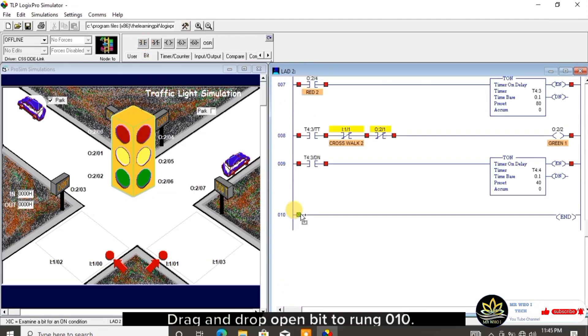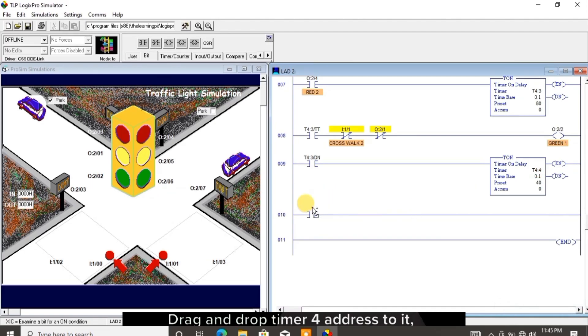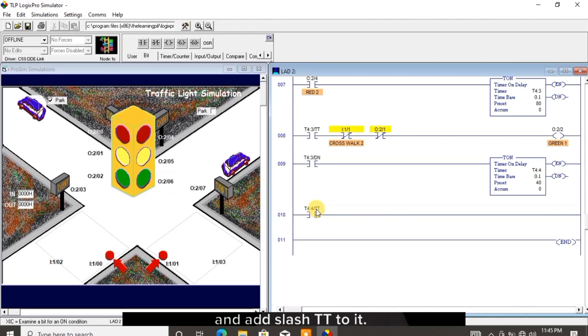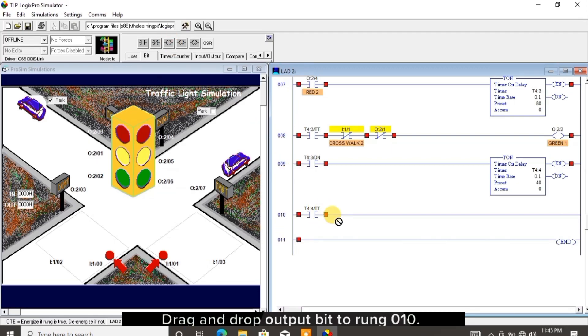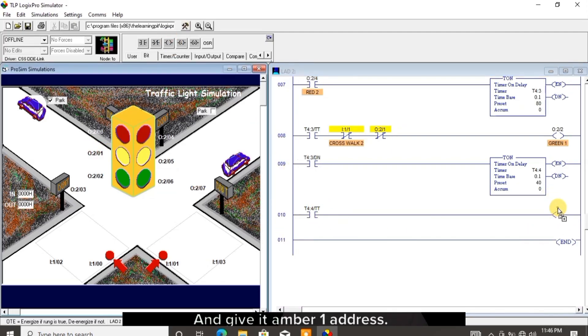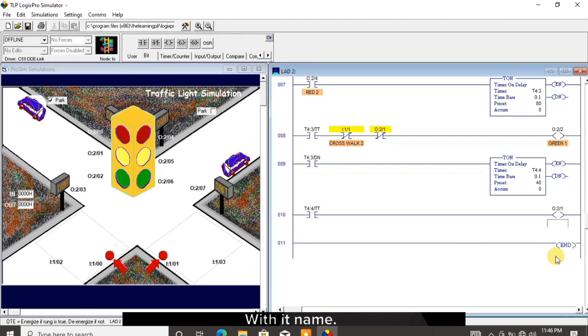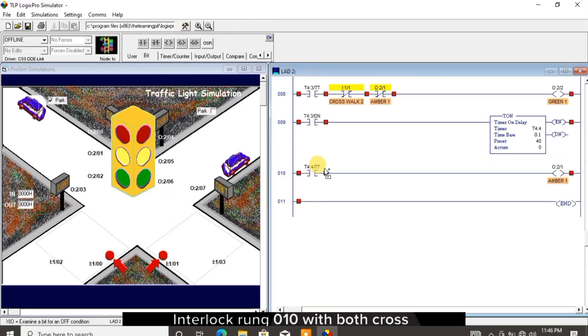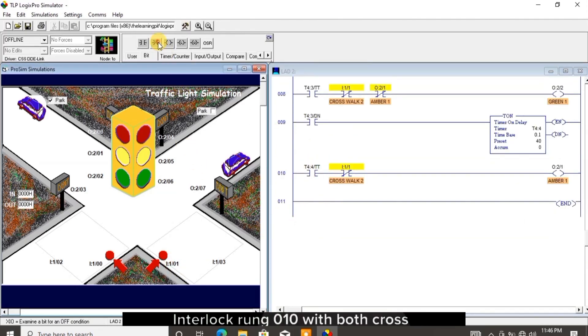I click on bit. Drag and drop open bit to rung 010. Drag and drop the timer 4 address to it and add /TT to it. Drag and drop output bit to rung 010 and give it the amber 1 address with its name. Interlock rung 010 with both crosswalk 2 and red 1.